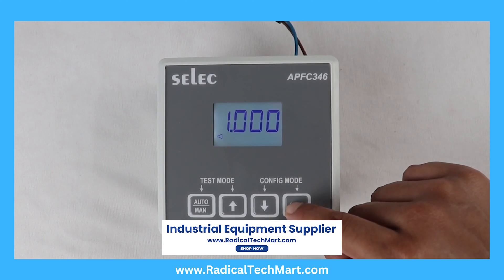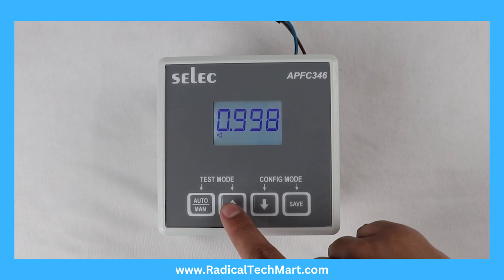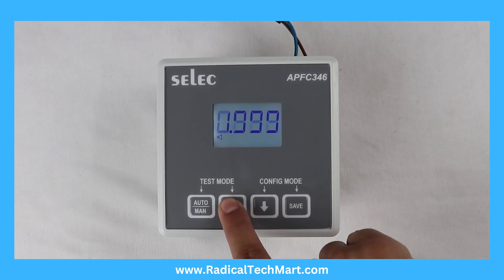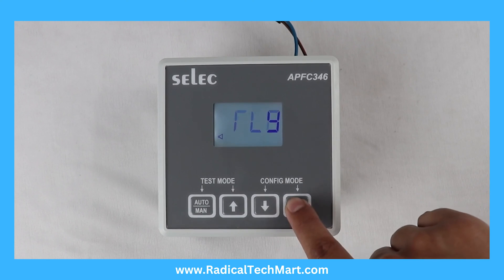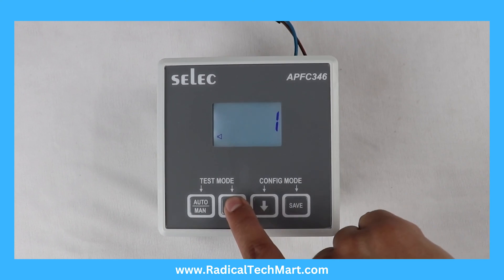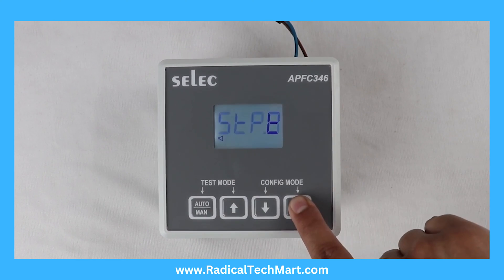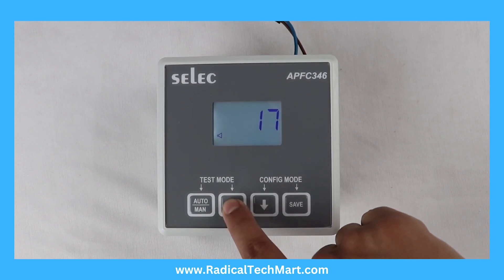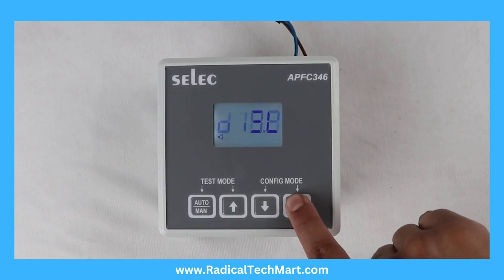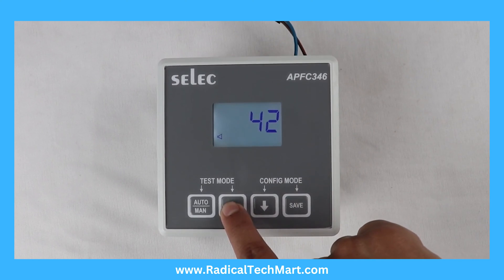Target Power Factor: set between minus 0.800 to 0.800. Relay Count: set between 1 to 12. Step Time: 1 second to 999 seconds. Discharge Time: 1 second to 999 seconds.